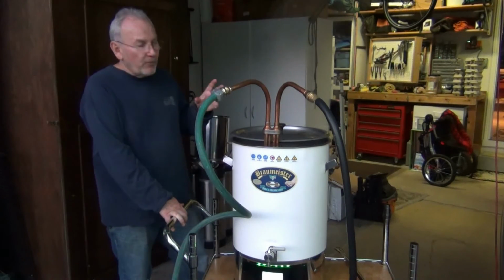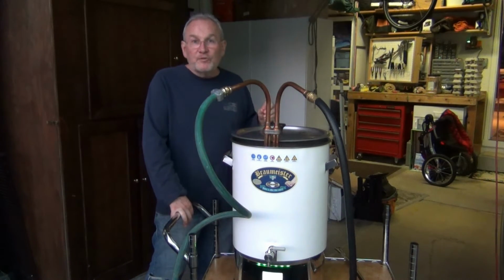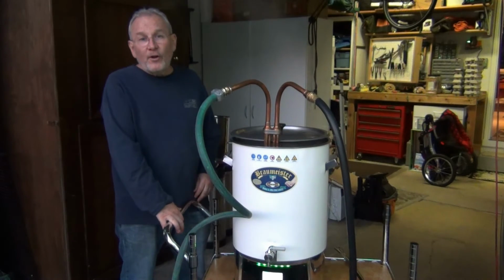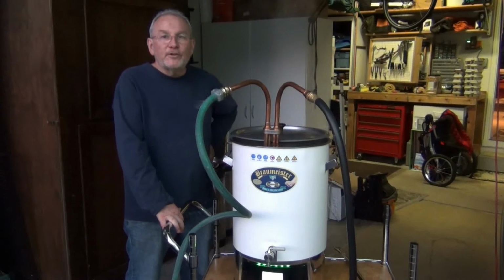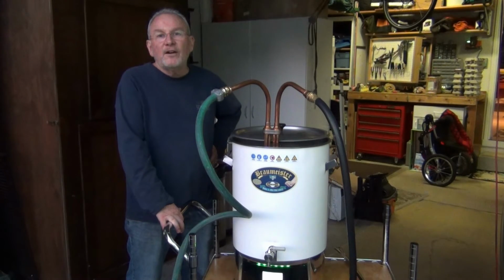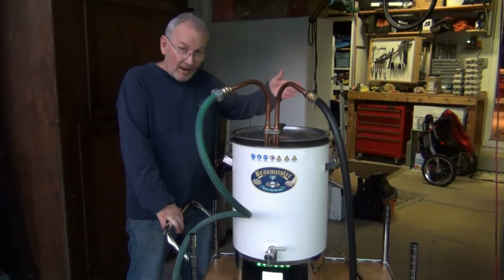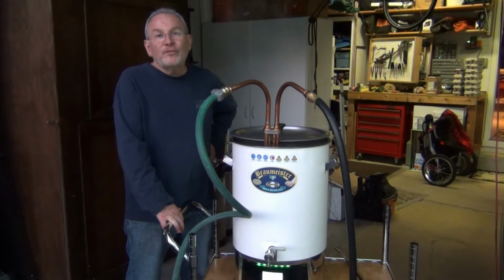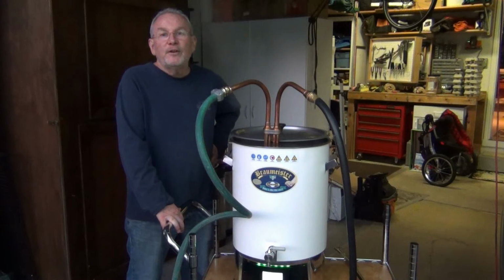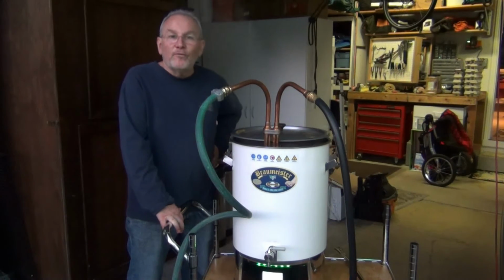So today we're going to be stirring it with a large spoon. And finally, the hose length: for any chiller, it's important to limit the length of the feed hoses, both coming in and going out. This allows for increased source water and discharge water pressure, resulting in greater flow rate.